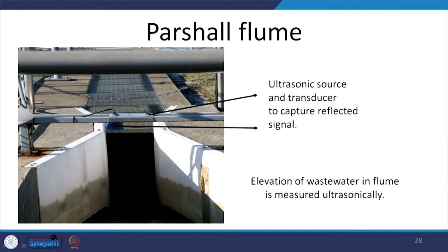So, they have an ultrasonic source, I guess, and a transducer to capture the reflected signal, to capture the depth. You can see the varying depth out here. So, the elevation of wastewater in a flume is measured ultrasonically here.